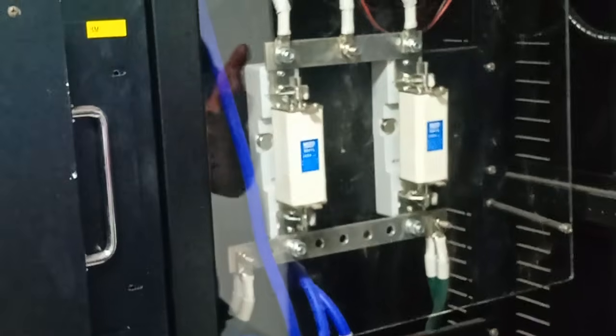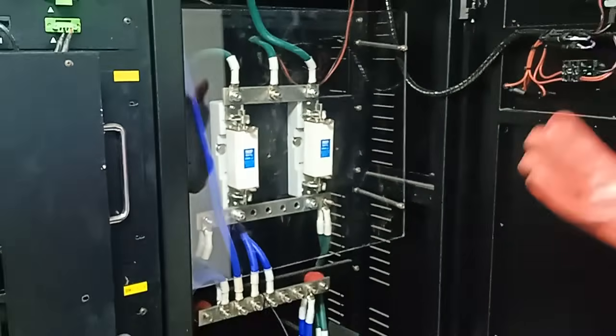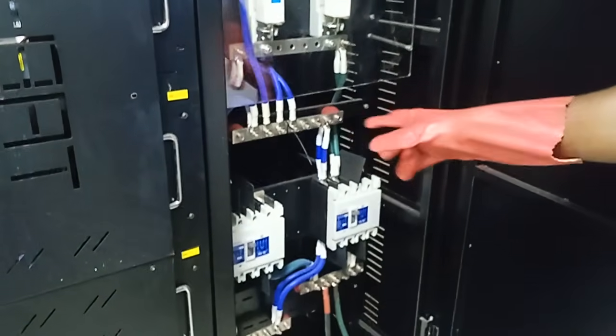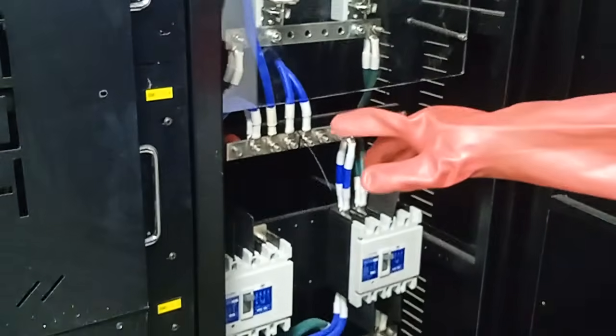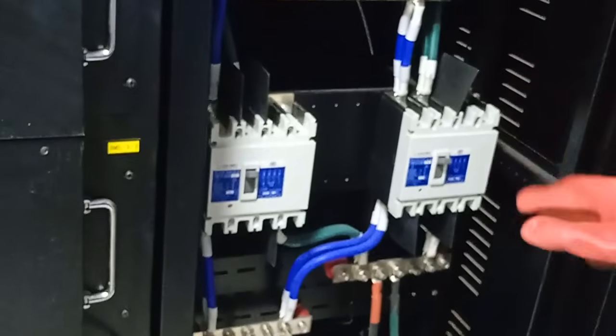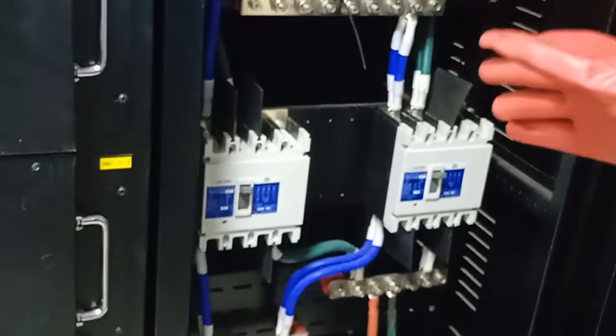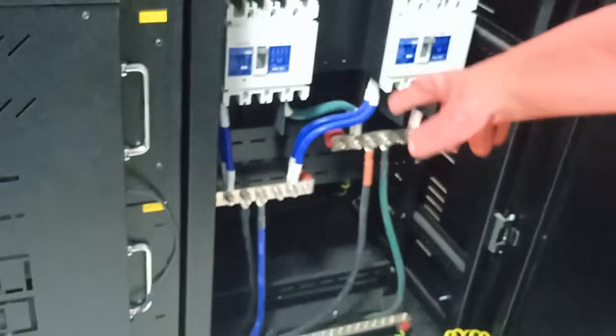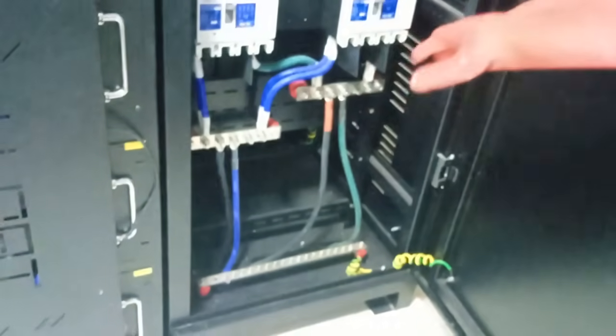Inside the battery combiner, you see the controller that manages all these batteries. Then you can also see where all these batteries are connected in parallel. For the positive terminal, we have two 250 amp fuses with 750 volts DC rating. And for the negative terminal, it is connected using a bus bar. You have 2 breakers for the batteries, which isolate the battery from the inverter. These lower bus bars are where the battery is connected to the inverter. Then this is the earthing for the battery combiner.